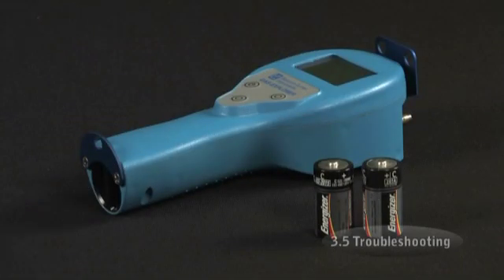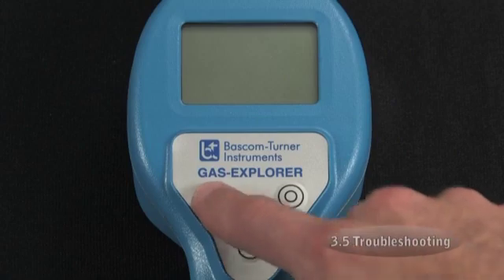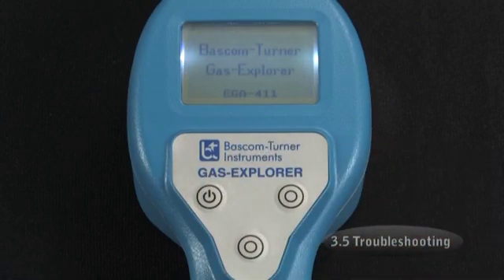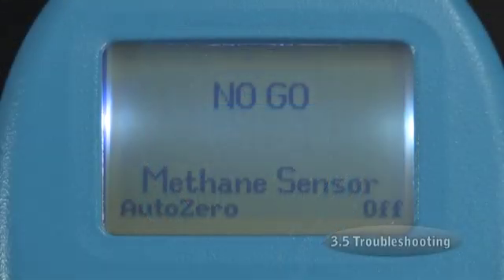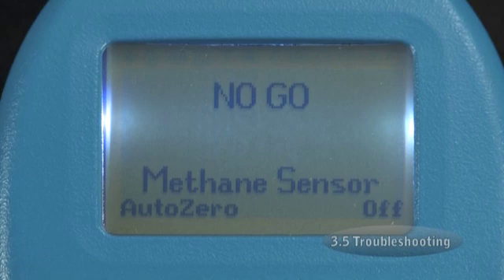The Explorer is a remarkably trouble-free instrument due to the automated routines that it goes through during startup. However, there are a few error messages that should be mentioned. The message "No Go" is displayed when you attempt to zero the Explorer in a gaseous atmosphere. Remove the instrument to clean air and attempt to re-zero.